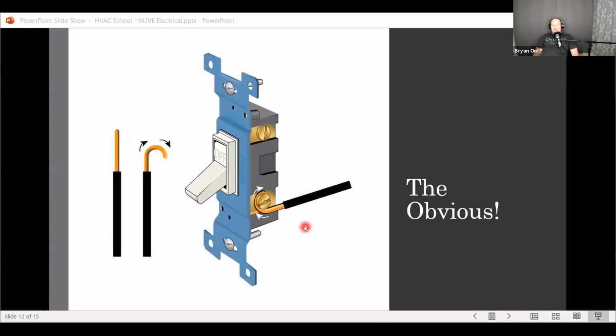Next thing is, I always want people to look for the obvious. I can't tell you how many times, and I use this is another image that I made for the folks in Haiti, how many times it's just the simple things that people do wrong, where they wrap it the wrong direction around a terminal, or they take a stranded wire and wrap that around the terminal, and then the stranded wire is coming off all over the place rather than using a crimp-on terminal, or they make a crimp-on terminal incorrectly, or they leave a bunch of bare wire exposed, or you have wires that are crossing one another, or crossing a discharge line or rubbing out on a piece of metal.